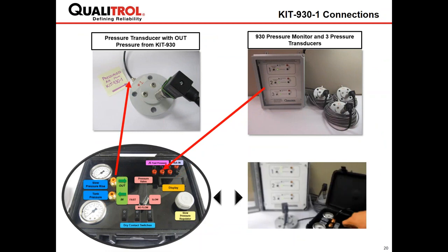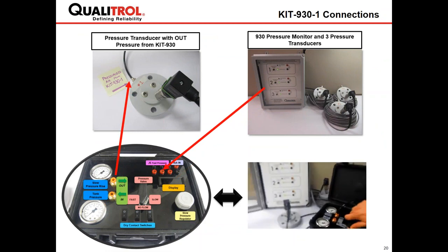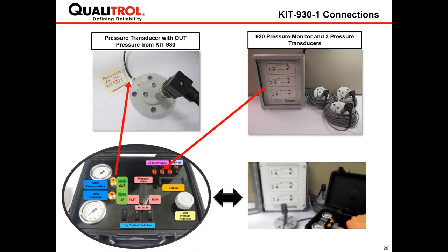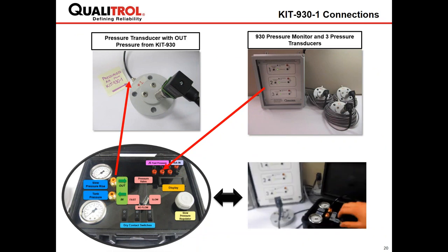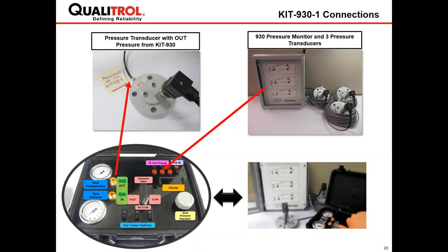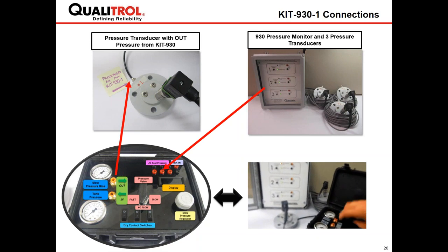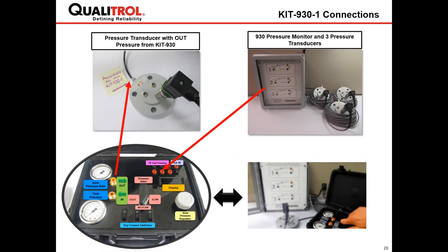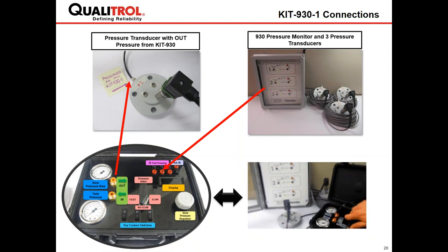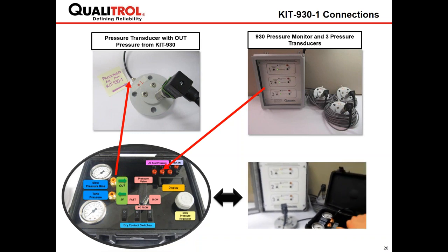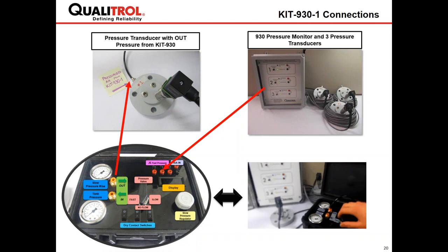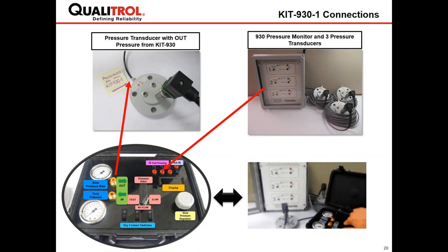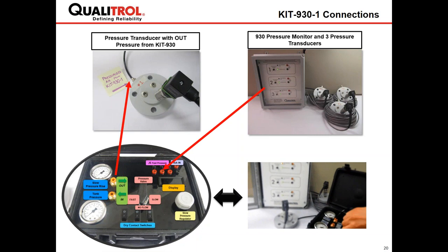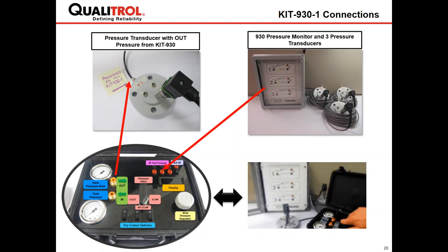Now here we have the face of the kit and some of the labels so that it's easier to look and explain as we go through the next 2 slides. On the left-hand side, you'll see that there's a pressure transducer with an out pressure that comes from the Kit 930. So that's a hose that is mounted to the top of the flange of where the transducer is mounted. And this will be on the side of your transformer. What you see displayed here is on a bench, but obviously in a real-life field instance, this is attached to your asset.